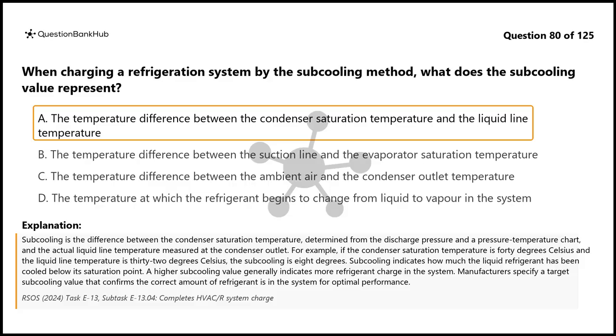Subcooling indicates how much the liquid refrigerant has been cooled below its saturation point. A higher subcooling value generally indicates more refrigerant charge in the system. Manufacturers specify a target subcooling value that confirms the correct amount of refrigerant is in the system for optimal performance.